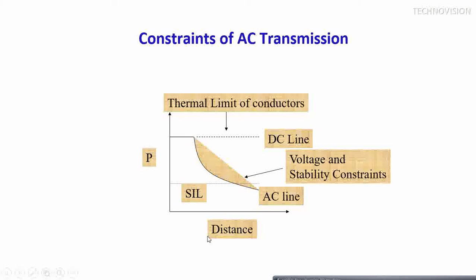This graph shows the relationship between distance and power transfer capability. As distance increases in AC transmission, issues of voltage and stability arise and the power handling capacity of the AC line reduces. That is not the case with DC transmission, which is independent of distance. There are HVDC links transmitting power over 3000 km — the longest link in China transmits over 3000 km using 1100 kV DC.